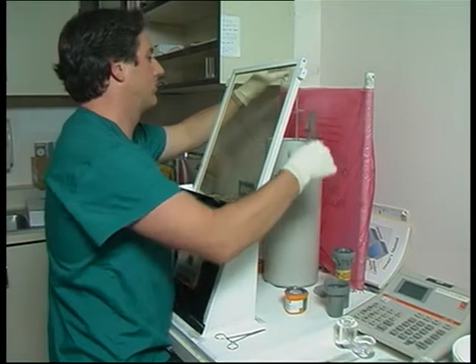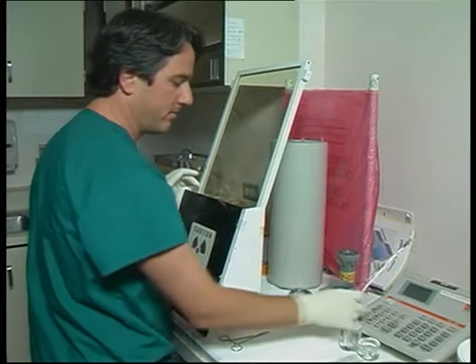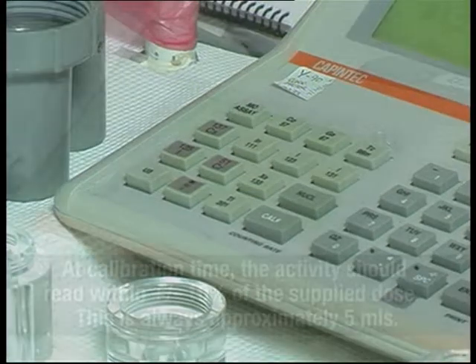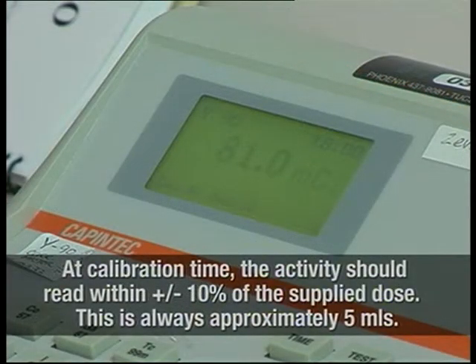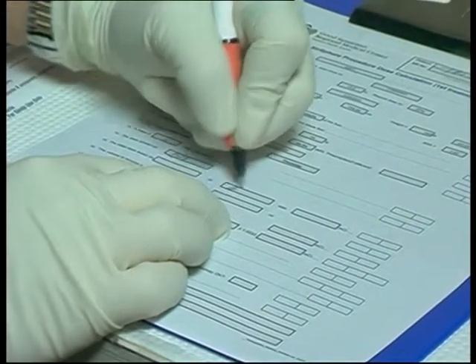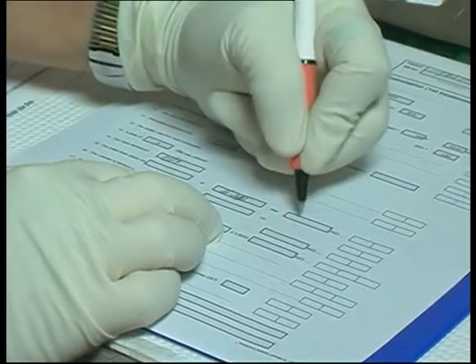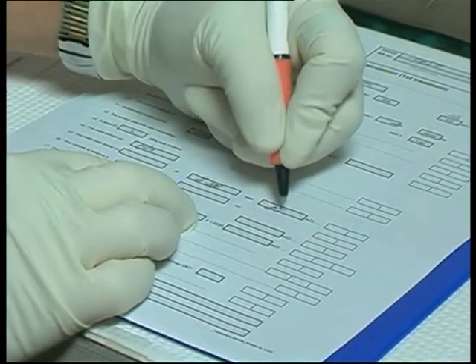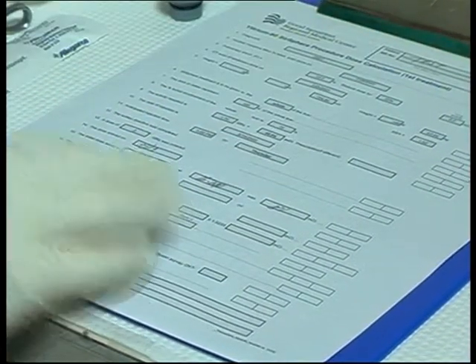Measure the activity of the SIR spheres by placing the shipping vial into a dose calibrator and press the button with the yttrium-90 setting. At the time of calibration, the activity should read within plus or minus 10% of the supplied dose. This is always approximately 5 milliliters. Record the reading. Please refer to the SIR spheres training manual for more information on calibration.